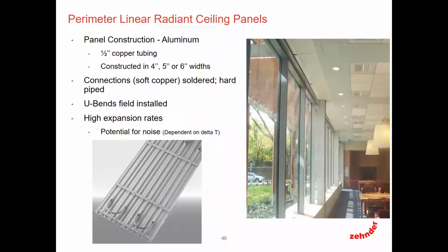Linear panels, these are linear extruded panels. They come in different widths, in 4 inch, 5 inch, 6 inch. Manufacturers offer different widths depending on each manufacturer. Typically, standard is aluminum construction with an aluminum saddle, and then the copper tube is fastened in that saddle on the back. These typically come with factory shipped loose U-bends and interconnects. So that's something to be aware of as a designer, what you're specifying.